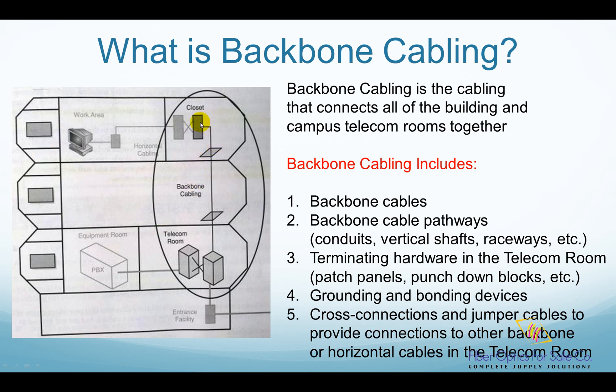This picture clearly shows what parts backbone cabling covers. It includes the backbone cables such as twisted pair copper cables and fiber optic cables. The backbone cable pathways support and distribute backbone cables, using conduits, vertical shafts, raceway, etc. The terminating hardware in the telecom room includes patch panels, punch down blocks, etc. It also includes grounding and bonding devices to ground the backbone cables that have metallic parts, and cross connections and jumper cables to provide connections to other backbone or horizontal cables in the telecom room.